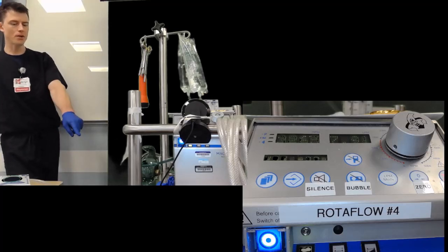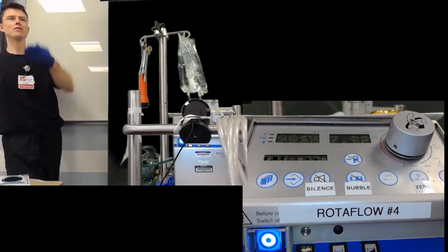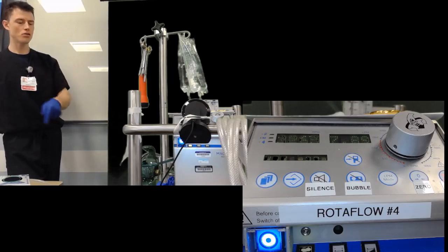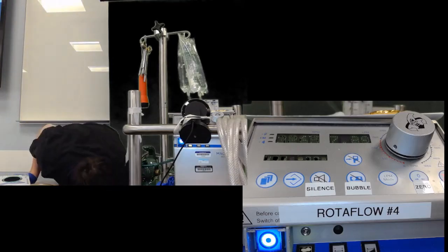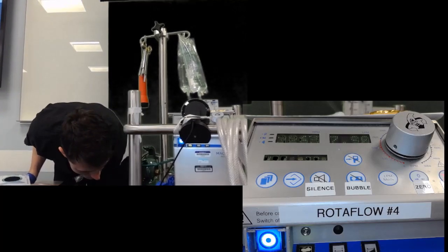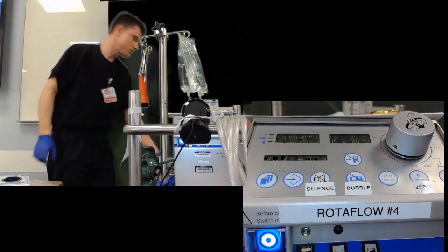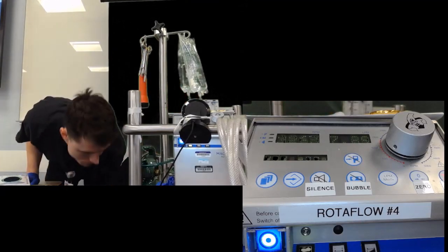So let's talk about that. If you have a patient who is either cold or hot on ECMO, that should raise your alarm bells. Why is that happening? That shouldn't be happening. So how do we troubleshoot that? We look at our heater down here. So this circulates water through the oxygenator. Okay, so it's hooked up here.